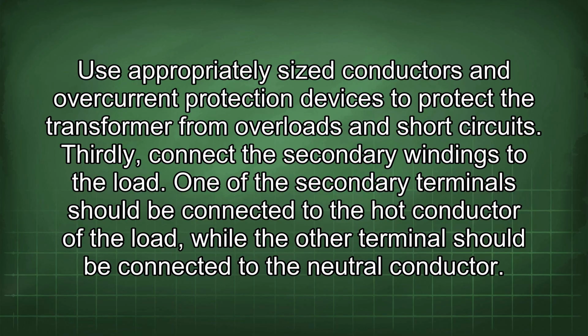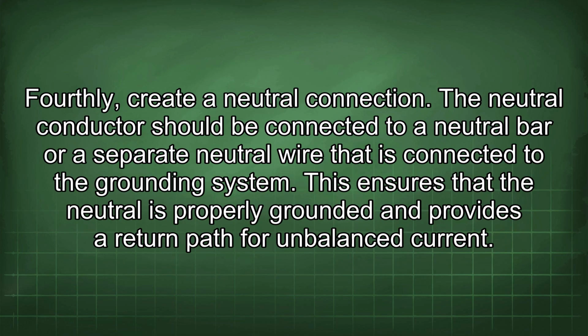Thirdly, connect the secondary windings to the load. One of the secondary terminals should be connected to the hot conductor of the load, while the other terminal should be connected to the neutral conductor. Fourthly, create a neutral connection. The neutral conductor should be connected to a neutral bar or a separate neutral wire that is connected to the grounding system. This ensures that the neutral is properly grounded and provides a return path for unbalanced current.